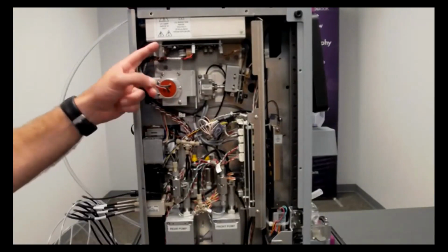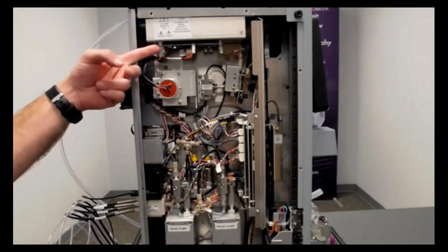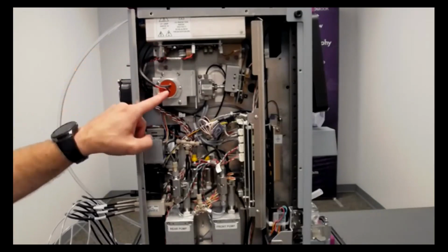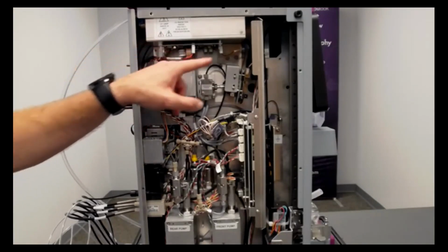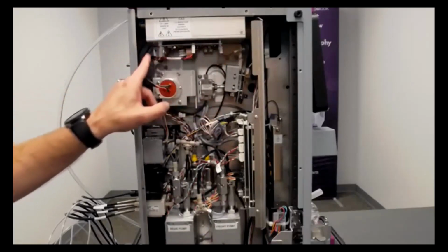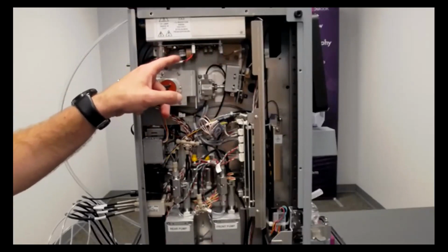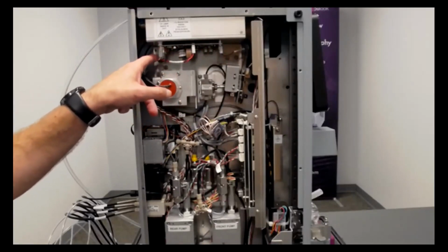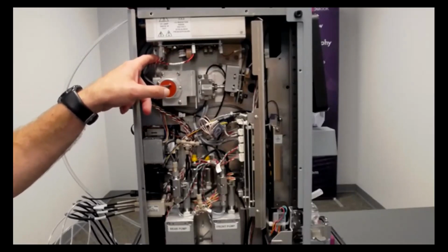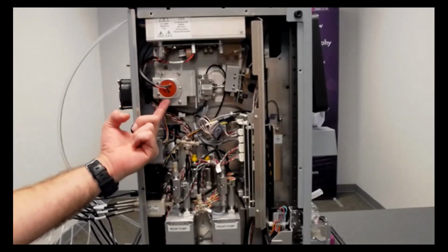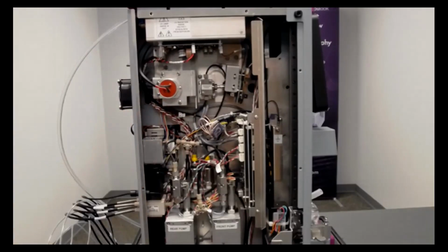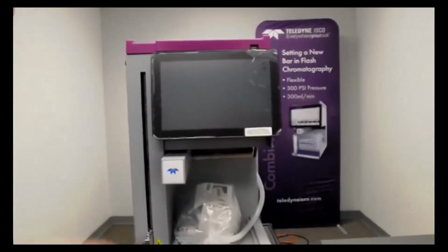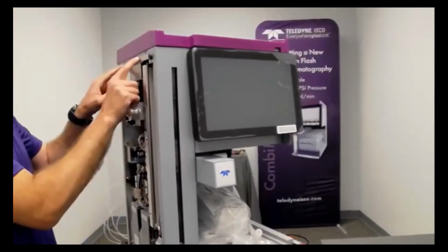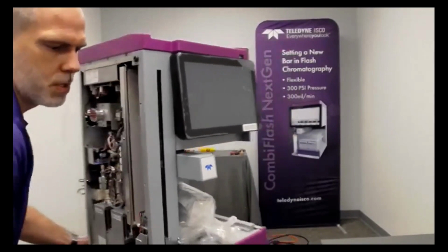Now up top, this is the lamp circuit board or the lamp driver board. This gives the voltage for the lamp to turn on. This receives a signal from the detector allowing the lamp to turn on. It powers the lamp fan, and there's a spot for the thermal sensor to plug in back here. Again, that thermal sensor is just physically attached to the lamp. All right, that's a quick rundown on what's inside there. Next, I'm going to take the top cover of this off. So we've already taken out 2 of the screws that hold the top on. So we just rotate it around.